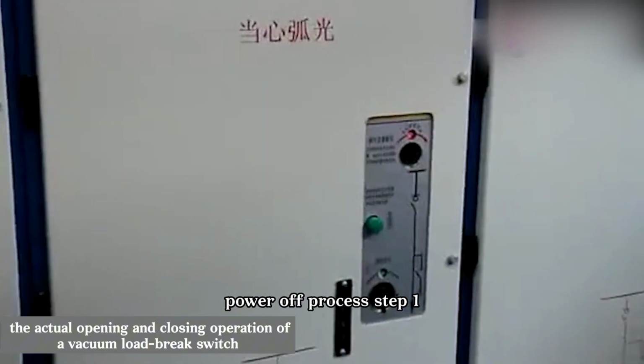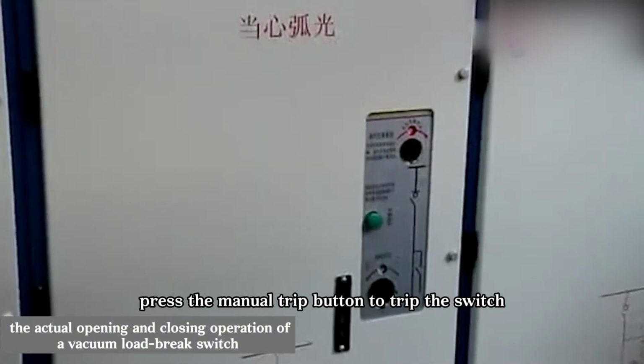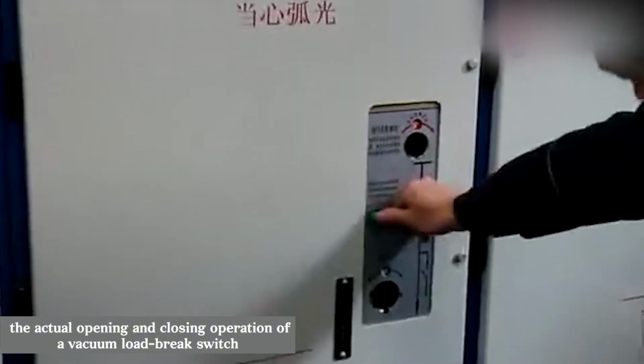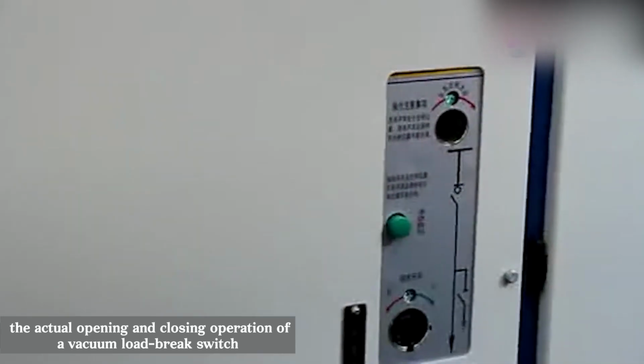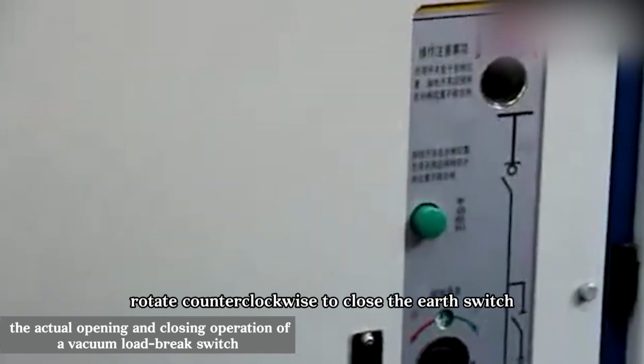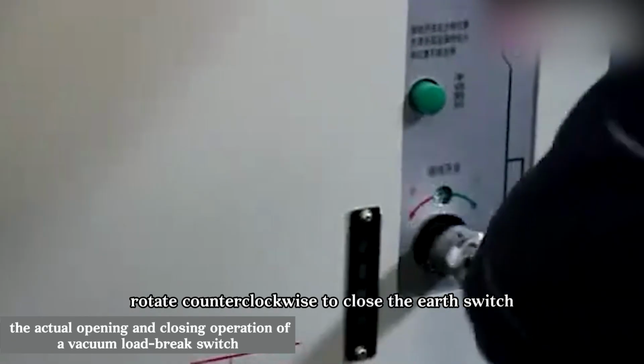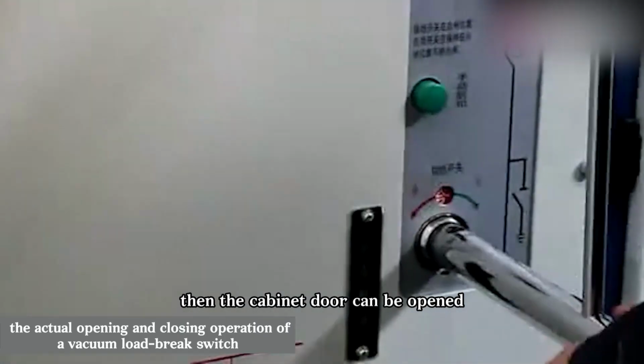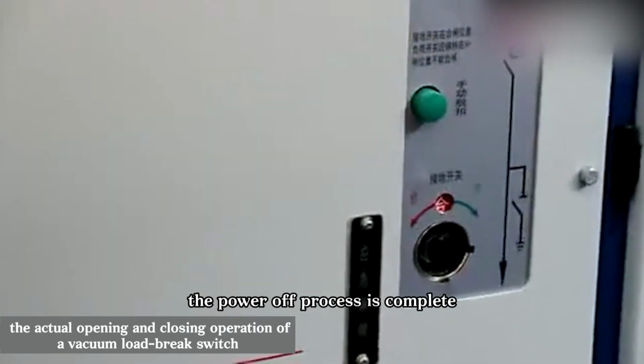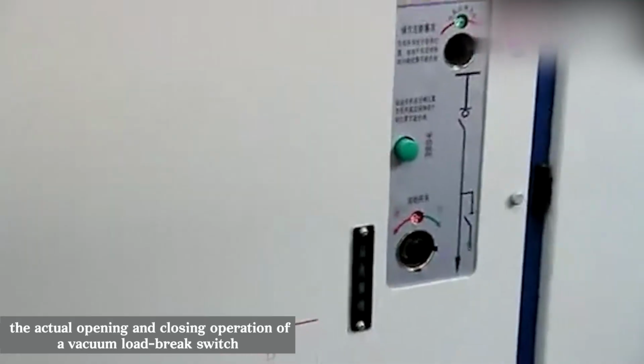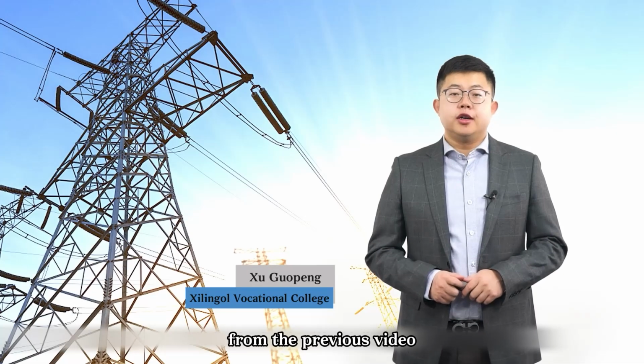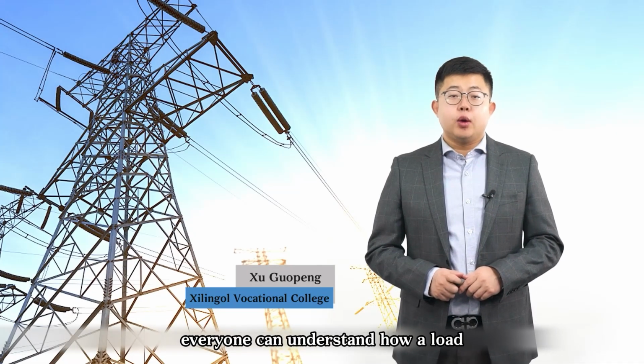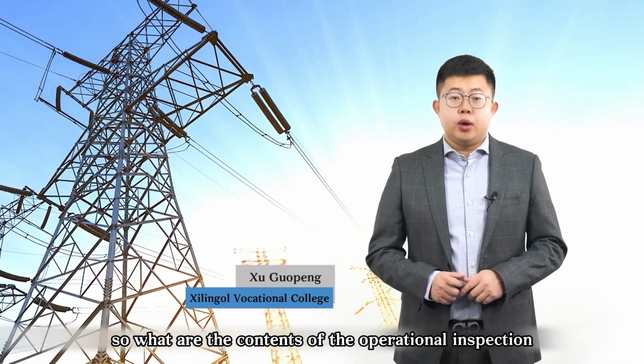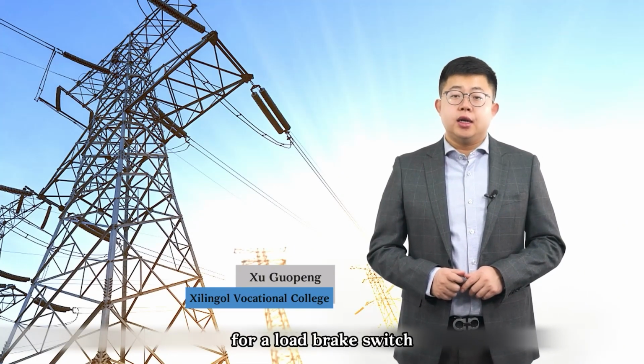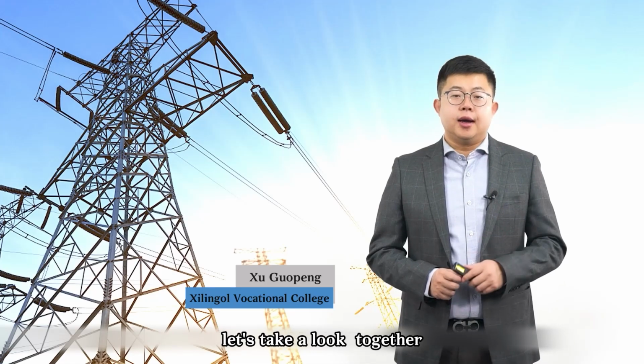Power off process. Step 1. Press the manual trip button to trip the switch. Step 2. Rotate counterclockwise to close the earth switch, then the cabinet door can be opened. The power off process is complete. From the previous video, everyone can understand how a load break switch performs opening and closing operations. So, what are the contents of the operational inspection for a load break switch? Let's take a look together.